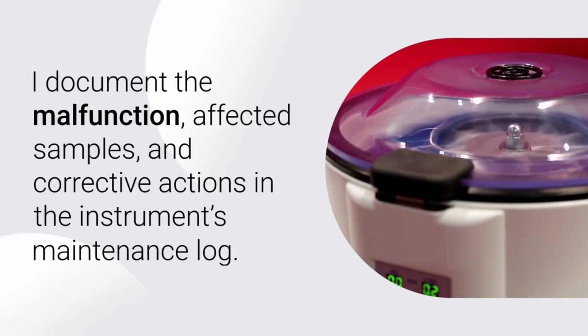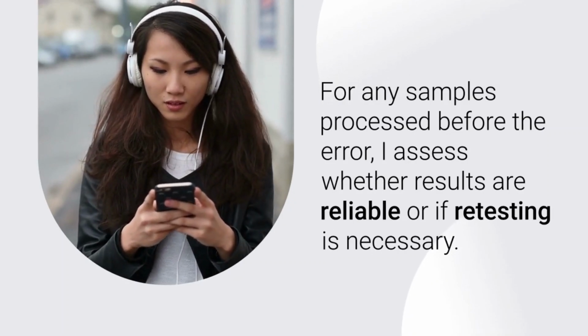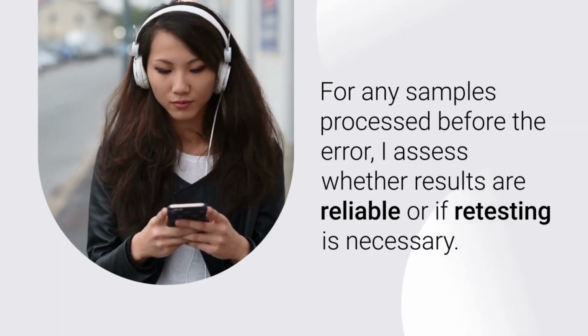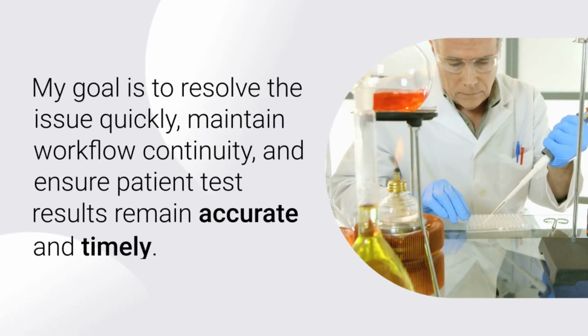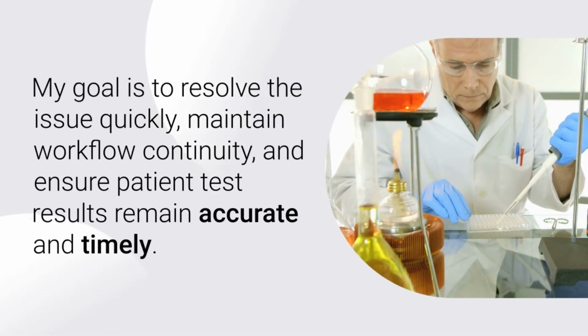I document the malfunction, affected samples, and corrective actions in the instrument's maintenance log. For any samples processed before the error, I assess whether results are reliable or if retesting is necessary. My goal is to resolve the issue quickly, maintain workflow continuity, and ensure patient test results remain accurate and timely.